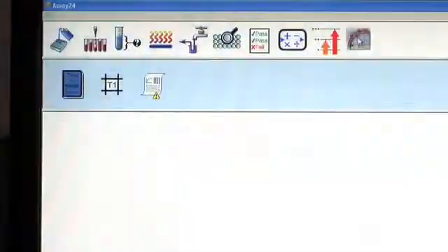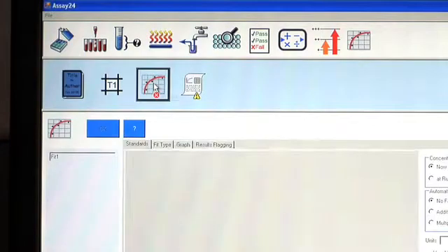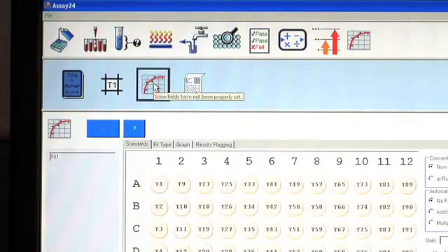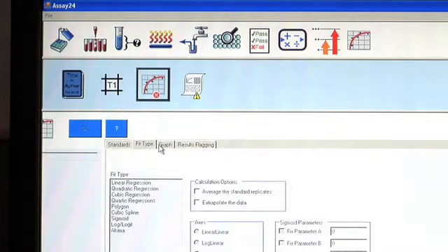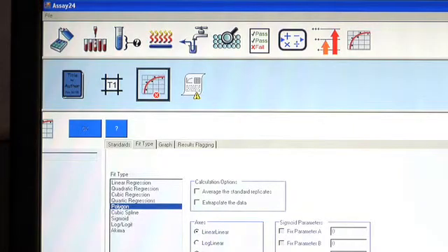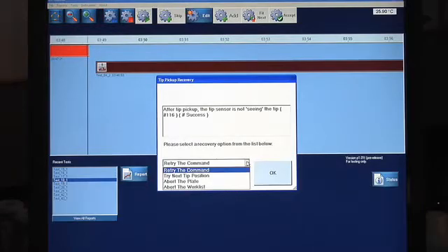The DS2 also enables recording and assurance of lot-specific data. Like the four-plate DSX, the DS2 offers open, versatile, and easy-to-use data reduction capabilities, including all commonly used curve-fit options, ratio calculations, quality control testing, and thresholding features. Audible alarms, error recovery, and integrated diagnostics are also standard.